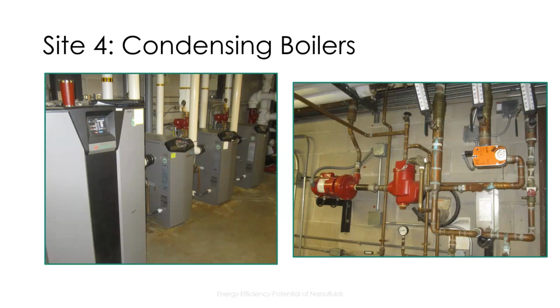Our fluid replacement process for this site involved replacing glycol in only 2 of the subloops, one of them that served air handler coils and another one that served the snow melt system, since these were the only closed loops available. The main heating loop remained unchanged in the pre and post with water, only due to our approach and how we wanted to estimate the load on the system. If we were to change the fluid in the main loop, it would compromise our loading calculation.